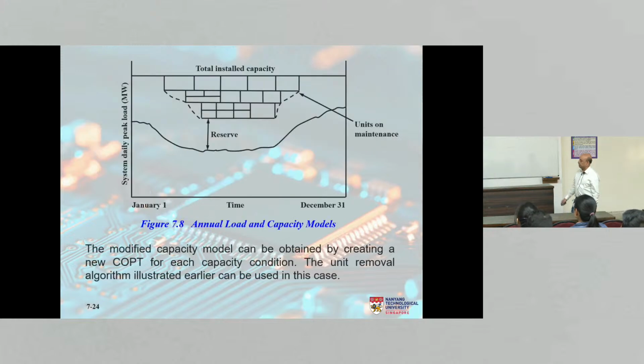So I'm going to show you this one first. So this is my load profile. This is the reserve in the system, and this is the total installed capacity. And let's say that these are the units on maintenance. At different times, of course. You don't maintain so many generators at the same time. You can see that from this period to this period, these generators are on maintenance. Then this period, more are on maintenance.